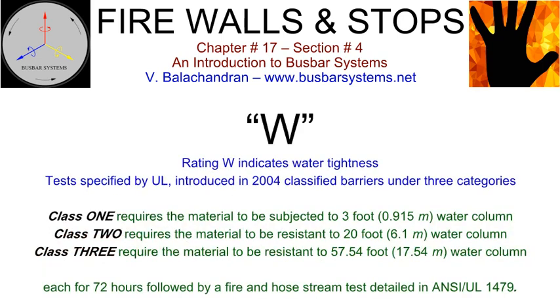Rating W indicates the fulfillment of water tightness requirements as per tests specified by the Underwriters Laboratories. This rating, introduced in 2004, classified the barrier under 3 categories. Class 1 requires the material to be subjected to 3 foot or 0.915 meters of water column for 72 hours, followed by a fire and hose stream test detailed in ANSI/UL 1479. Class 2 and Class 3 require the material to be resistant to 20 foot or 6.1 meters and 57.54 foot or 17.54 meters of water column respectively.